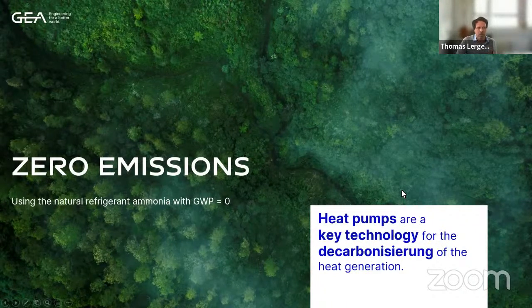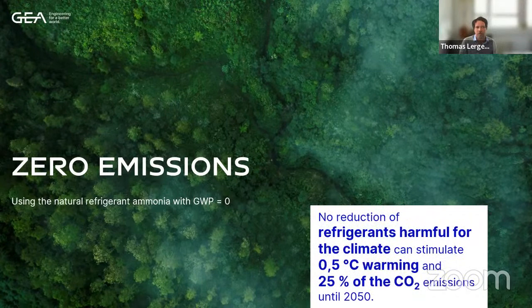Because if we do not reduce the use of harmful refrigerants, this can contribute 0.5 degrees of global warming and up to 25% of all the CO2 emissions within the next 25 to 30 years. So using natural refrigerants with a low global warming potential, or ideally zero global warming potential, helps a lot. Ammonia is also very efficient in our application range. So on top of the ecological advantages, you also have economic advantages, as we can see in a bit.